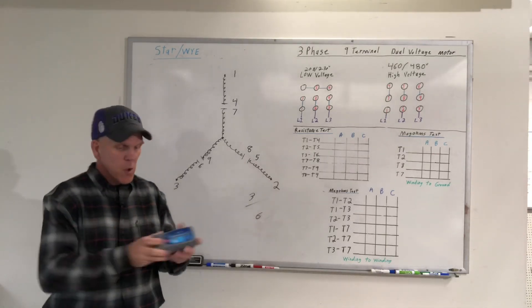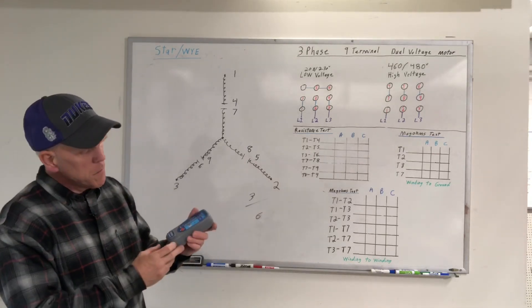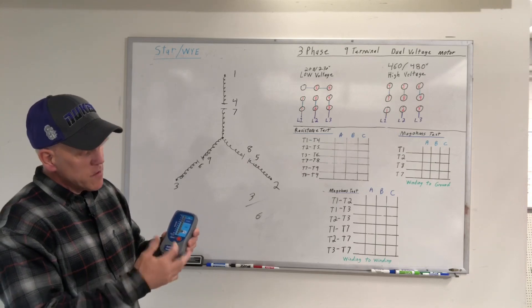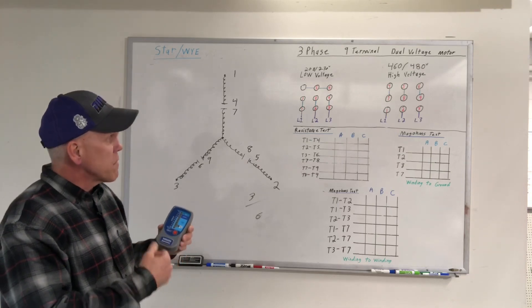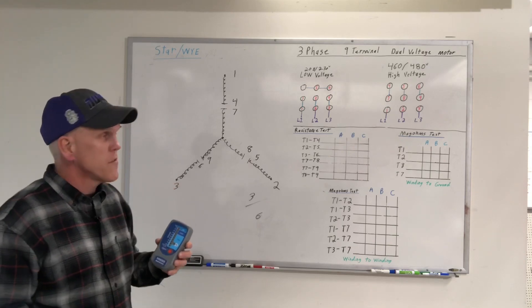What I'm going to be using today to do my mega ohms is going to be an M500. So when I come back, it's a Supco. When I come back, if everything is high resistance, which I hope to see, I'm just going to come back and put a check mark in them.